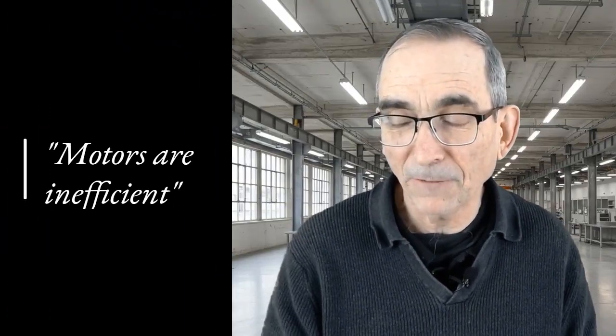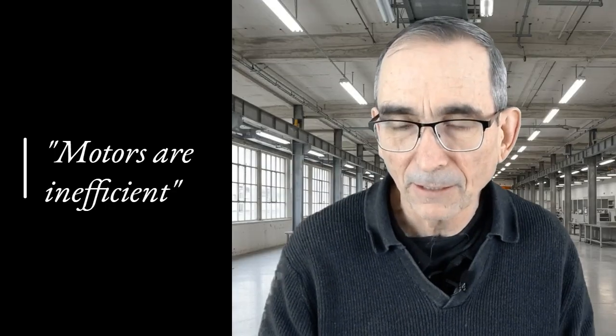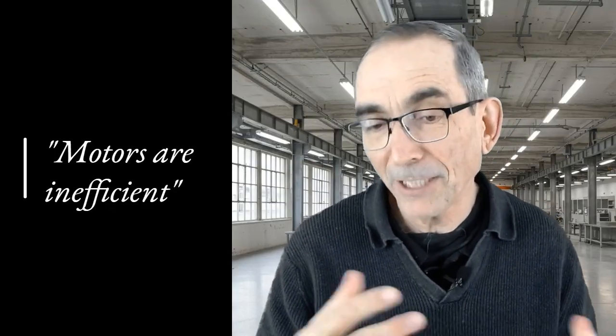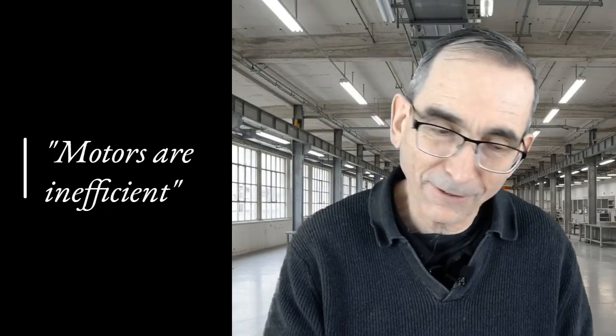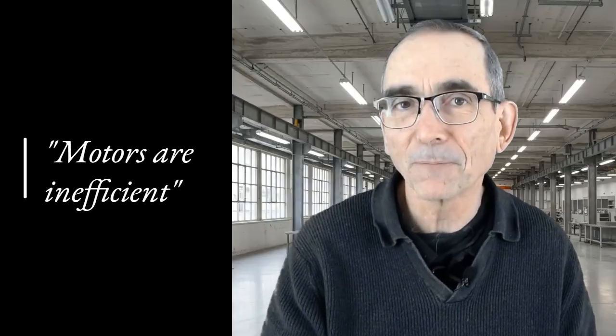And then another common one that really bugs me a lot actually is the assumption that you just need to upgrade the motors from, say, an IE2 motor to an IE3 motor, under the assumption that motors are inefficient. Well, most of the induction motors in a facility will already be pretty efficient. Going from IE2 to IE3 may only save you a couple of percent of energy, 1 or 2%. It's not much. Usually the big wins actually come from system efficiency, not just looking at motors themselves, but looking at the system that motor helps power.